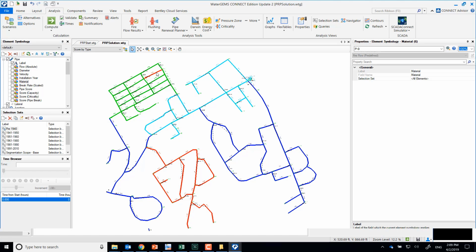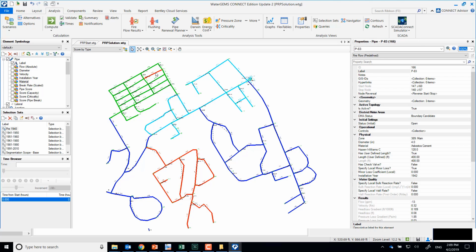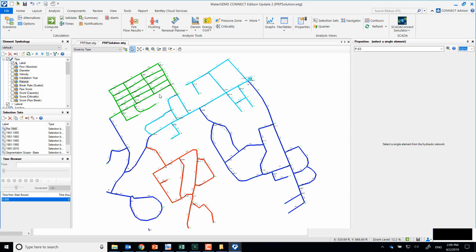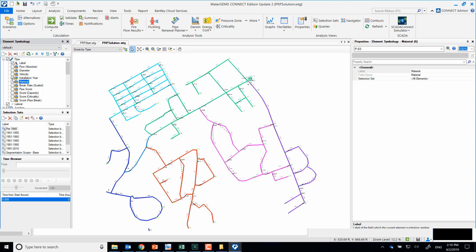Okay, and we'll take that into account when we're doing pipe breaks, because remember we were going to bring personal history to each of our pipes and say how many times they've had breaks in the past. But if a pipe did not have breaks, in order to help extrapolate or project when it will break, we're going to use a projected rate for the group that share the same material. So if a pipe material tends to break quite a bit, then it will increase the likelihood that one of those pipes would break. Okay, and we also had information as to what year those pipes were installed.